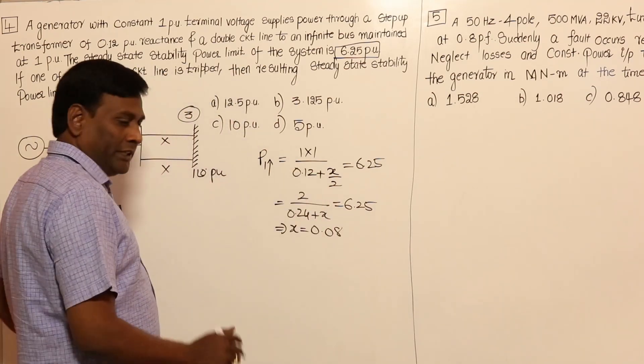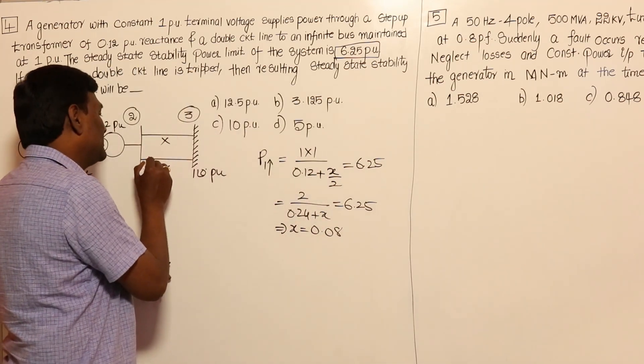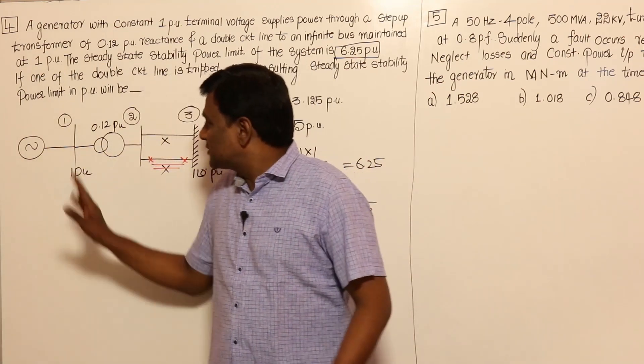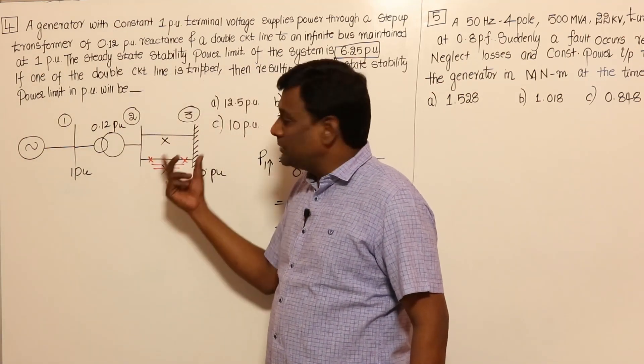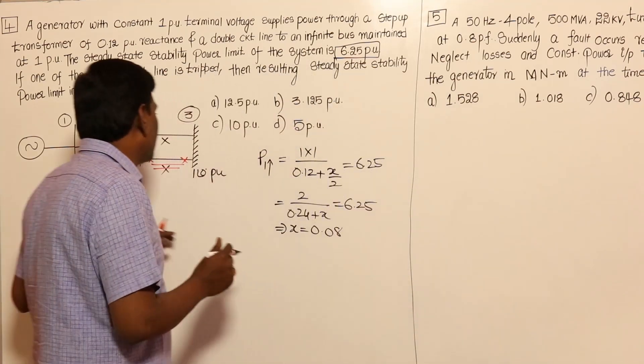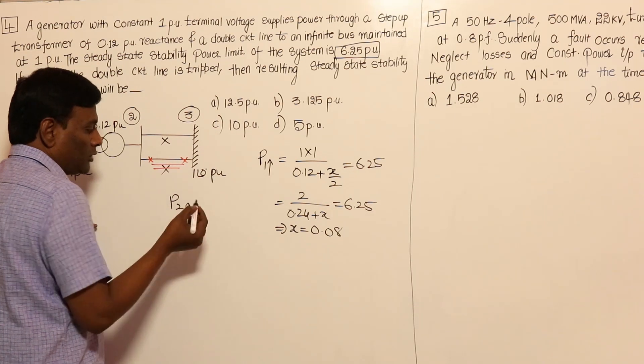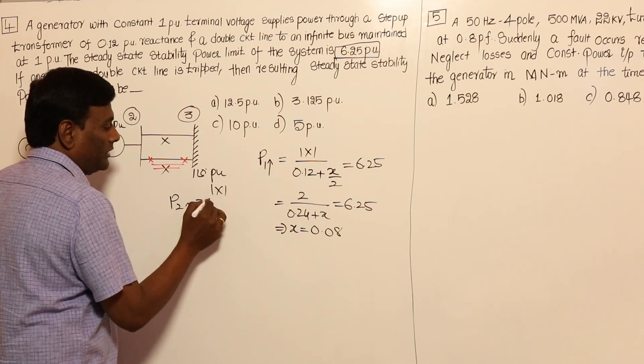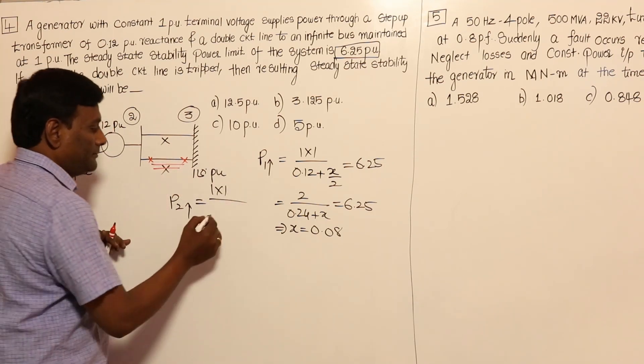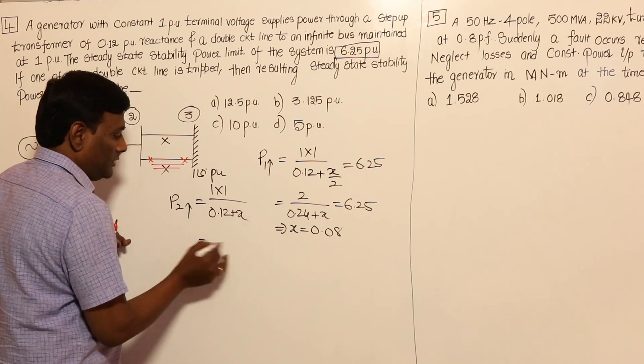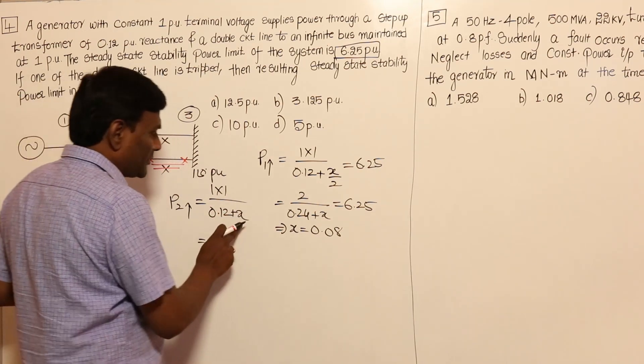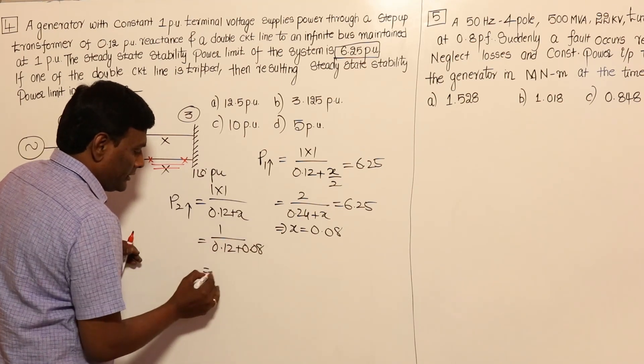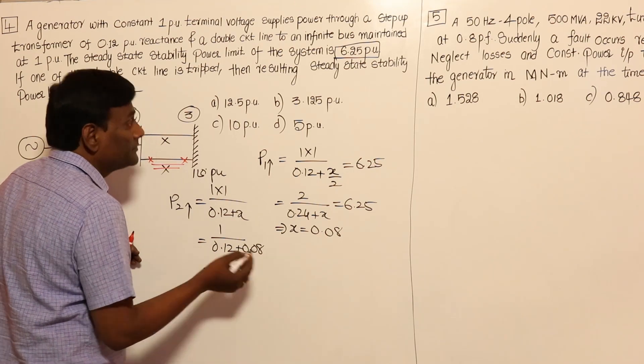Now, if one circuit is tripped, that line is completely removed. Under that condition, the reactance from sending end to receiving end is 0.12 + X only. So P2_max = 1×1 / (0.12 + 0.08) = 1 / 0.20 = 5 per unit.